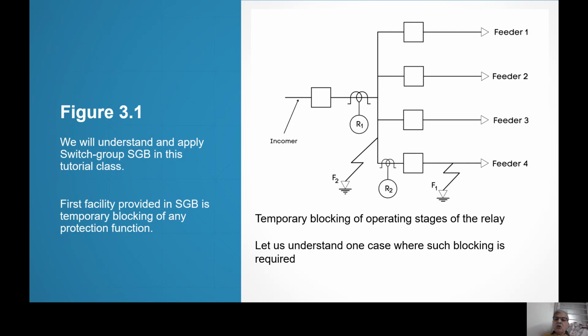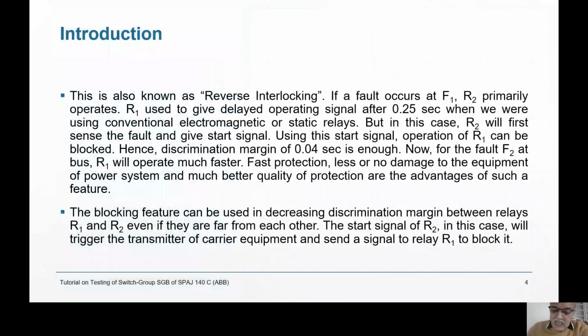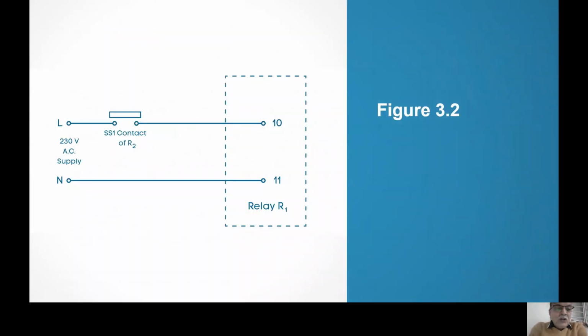Now, this blocking can be automatic also. It's not necessary that you have to block manually. Right. So this automatic blocking is done like this. All that I have told is written in these lines. You can read afterwards, right? What we are doing? The start contact of R2 gives a start contact. I was telling you that the dry contact is available when the relay starts. Starts means senses. Try to understand. The relay has not operated. It has only sensed the fault. It has started. So the start output is given to terminals 10 and 11, which are meant for binary input of relay R1. So relay R1 is given 230 volt AC, and I use SGB to block relay R1.